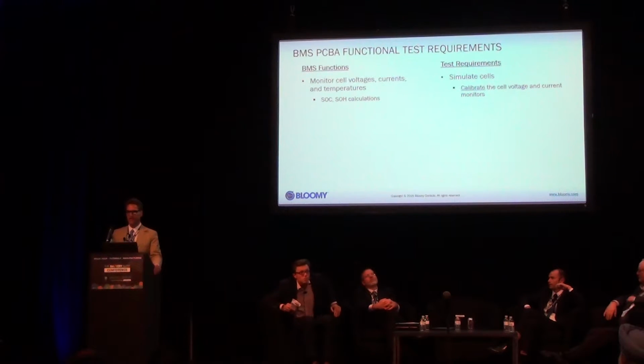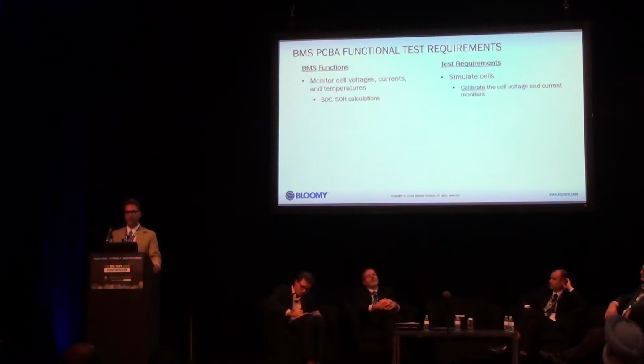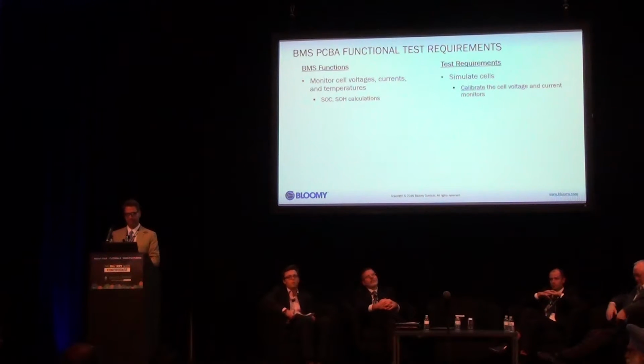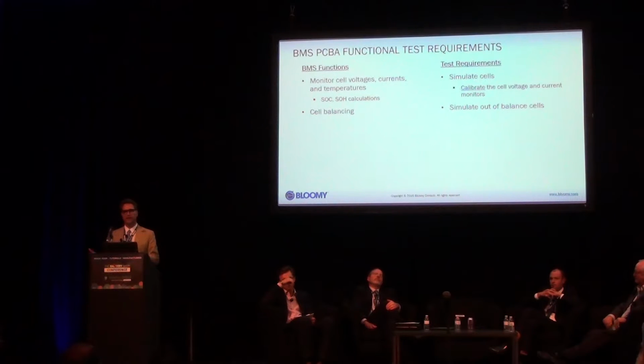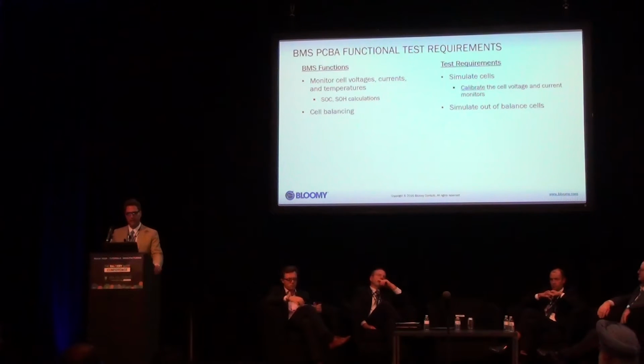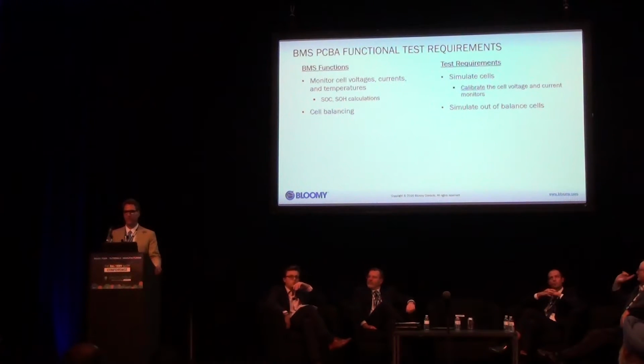Okay? So your test system needs to simulate cells in order to accurately verify that the cell monitors are working. In addition, you can calibrate the cell voltage and current monitors in your functional test system. And that usually corresponds to deriving some coefficients that you would download to the FPGA or the PIC microprocessor or somewhere on the BMS.